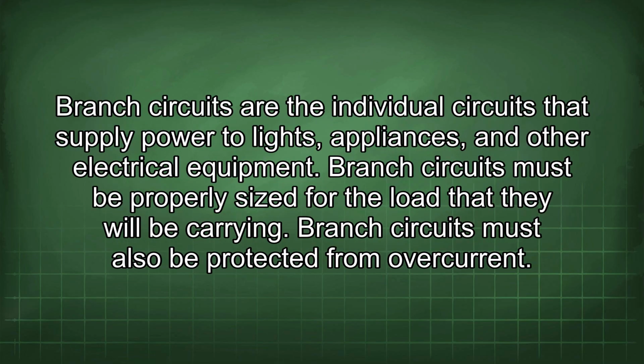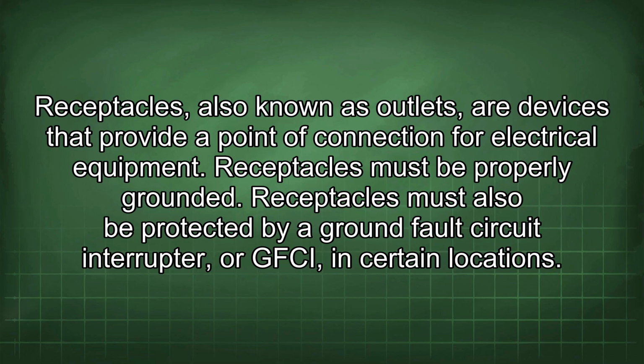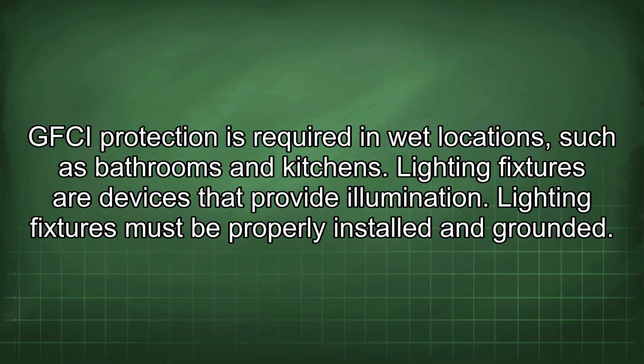Branch circuits are the individual circuits that supply power to lights, appliances, and other electrical equipment. Branch circuits must be properly sized for the load that they will be carrying. Branch circuits must also be protected from overcurrent. Receptacles, also known as outlets, are devices that provide a point of connection for electrical equipment. Receptacles must be properly grounded. Receptacles must also be protected by a ground fault circuit interrupter, or GFCI, in certain locations. GFCI protection is required in wet locations, such as bathrooms and kitchens.